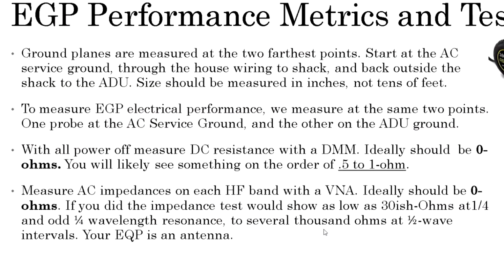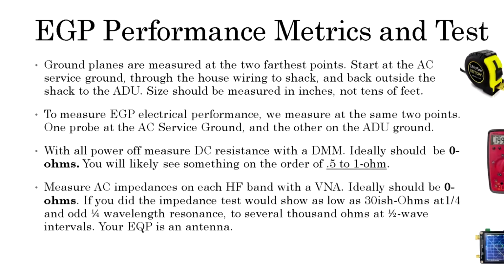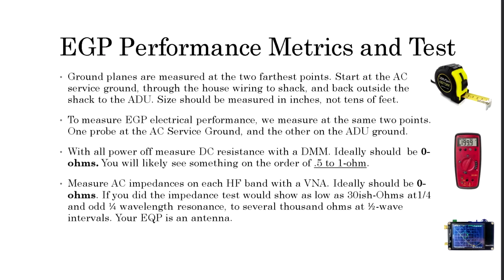Okay, we can measure the performance of your equipment ground plane. To do it, we have to measure at the two furthest points of the plane. So a typical plane is going to start at your AC service ground, and the other end of it is going to be several feet away, outside the shack window at your ADU. That could be, I don't know, as short as 20, 30 feet, maybe as long as 100 feet, if not a little longer. Point is, it should be measured in inches, not tens of feet.